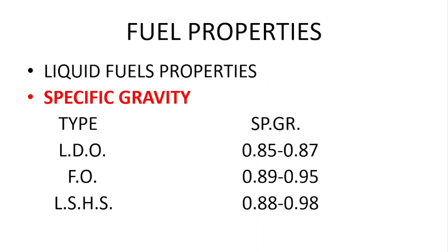Liquid fuels have the following properties: specific gravity. LDO specific gravity is 0.85 to 0.87. Furnace oil, the specific gravity is 0.89 to 0.95, and LSHS, the specific gravity is 0.88 to 0.98.